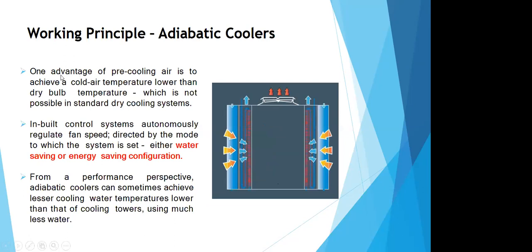So if you look at the working principle, the pre-cooled air achieves a far lower temperature than the dry bulb, which is not possible in standard dry cooling systems. So we can achieve temperatures very close to the ambient wet bulb temperature and cool down the fluid within the coils, and the heat is in turn exhausted through the fan. So you can see in this picture the arrangement of the evaporative pads through which the air is cooled. And this part of the unit is where the coil is kept, which contains the fluid, and that gets cooled, and the air picks up heat and then is exhausted through the fans.